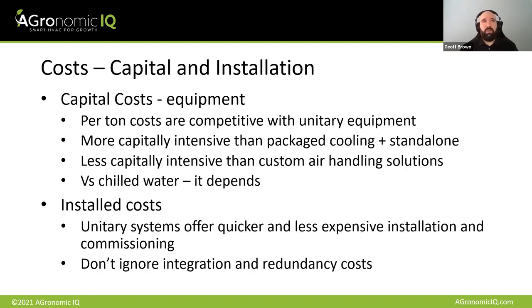Just in general terms, capital costs are the cost of the thing that you're buying. So when we're looking at this, there's a bunch of different categories of equipment that you can buy. In general terms, the AGronomic IQ product line is a unitary piece of equipment. It's designed as a single piece of equipment that handles the entirety of your grow room's HVAC demands: heating, cooling, and dehumidification. And we're cost competitive with unitary equipment, but we're going to be more capital intensive than packaged cooling equipment, a typical York, Carrier, Lennox rooftop, plus standalone dehumidification. We're going to be significantly less expensive than a true custom air handling solution. And then there's the chilled water boogeyman that sort of exists in the corner. And that's a big, it depends.